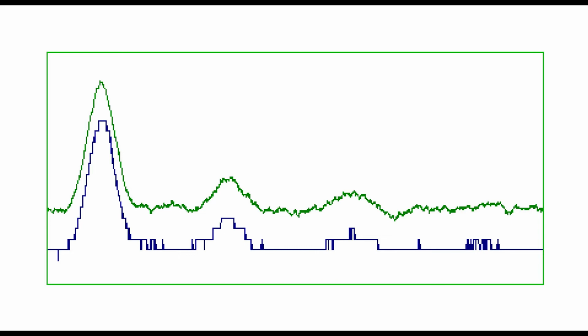If the specified data sampling rate is less than the minimum that the hardware can support, then the hardware will run at its minimum rate and data points will be averaged, bunched, to lower the data rate to, or near, the specified value. This averaging also reduces the apparent step size as seen in the raw file. However, it should not be thought that averaging improves the resolution. Because each data point is separately rounded to the nearest step before averaging, the round-off noise is not significantly reduced.